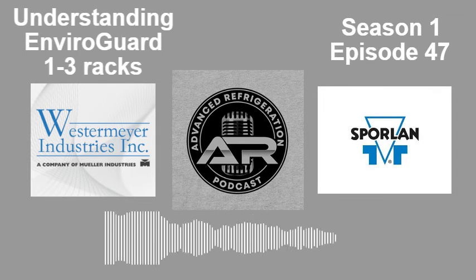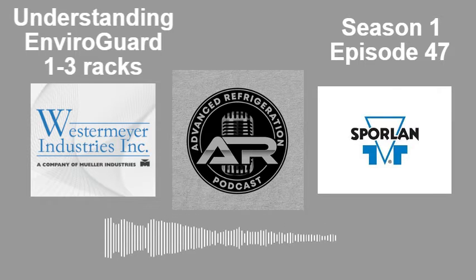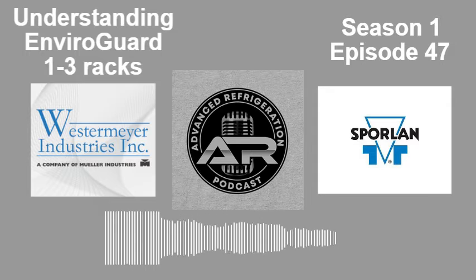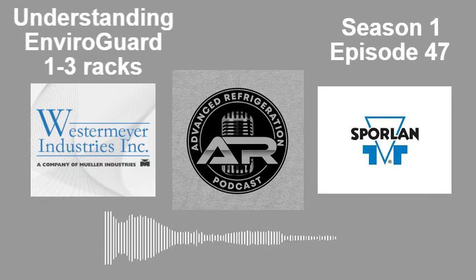So where you may need 4 compressors to run, now you're doing the work with 2 compressors. That boatload of subcooling made those compressors more efficient. You were able to do more work because you have that colder liquid. That liquid's going a lot farther in those evaporators, and your compression ratio is like nothing.